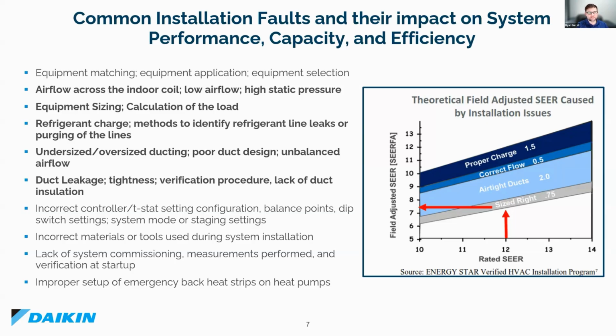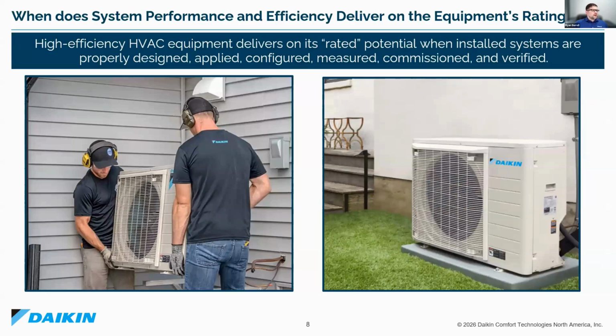Homeowners are purchasing 13, 14, 15, 16 SEER equipment every single day, and they are truly only getting, potentially, 6, 7 SEER, or the equivalent, because of all these installation issues. All right, I'm going to highlight a few. So when does that system performance and efficiency deliver on those equipment ratings?